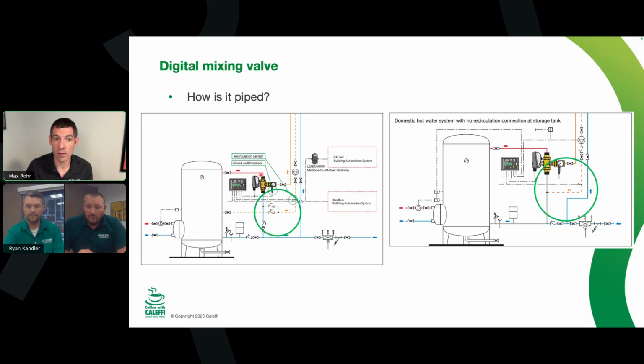That's fantastic. We don't need to always engage the full volume of the tank. If the recirc line is still warm, let's just send it out for another lap and then top it up, instead of going all the way through the tank to engage that whole volume and potentially stir up the stratification of the tank. So as you were describing too, if we have, coming back to the cold inlet, a check valve pointing up in this piping diagram right here, that's an easy mistake to make. And we don't want that, because we want the water coming back from the recirc line to be able to go up or down in this scenario.